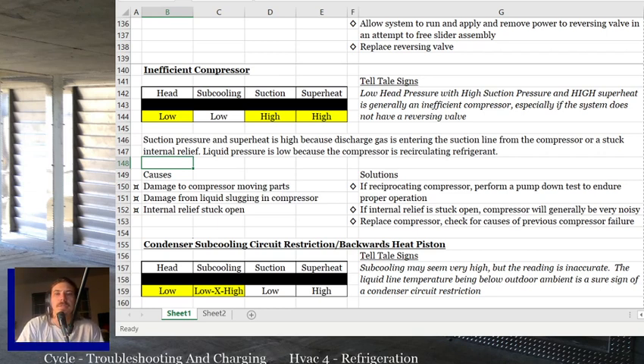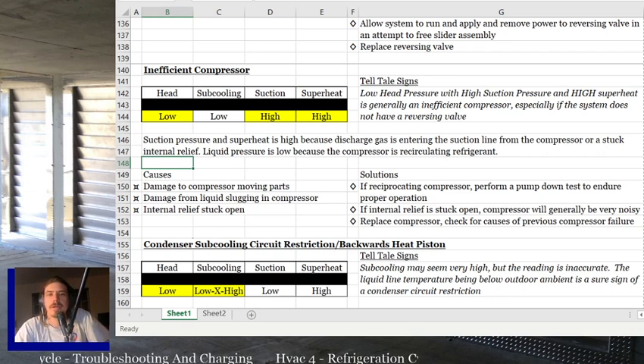Or the internal relief is stuck open. That's what you're usually going to see on a scroll, and generally it's going to be real noisy. Scrolls don't have valves, right? They have plates. The plates could be damaged, and that can cause an inefficient compressor issue. But the other thing that can happen is that the internal relief inside the scroll can get stuck partially open, and it'll just be bypassing gas all the time. So if a system's run with high head pressures for a long time, and that internal relief's constantly opening up and gets stuck open a little bit, the next thing you've got is an inefficient compressor.